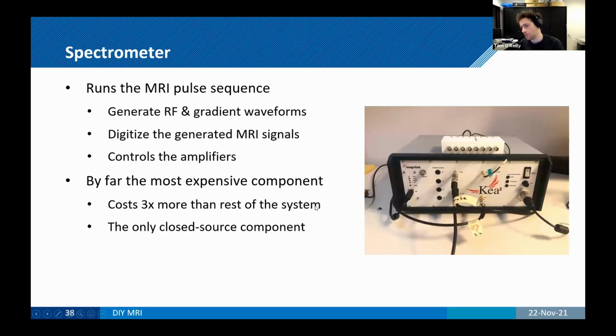And then finally, the spectrometer. That's what you're actually going to run your MRI pulse sequences on. It generates the RF and the gradient waveforms and digitizes the signals coming in and things like that. At the moment, this is by far the most expensive component of the system. It is made by a German company called Magritek. It's about 25,000 euros, which is 3 times more than the rest of the system combined. So we are planning on replacing this eventually with an open source alternative, but it's taken a lot of work.